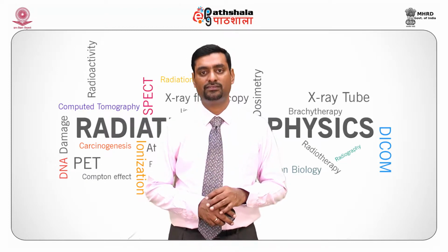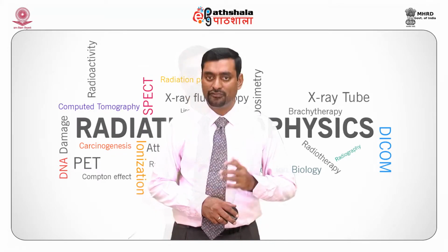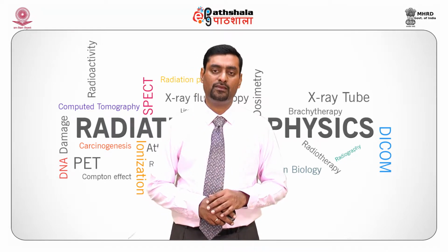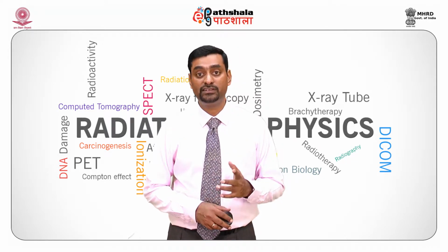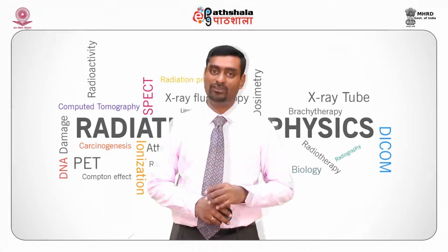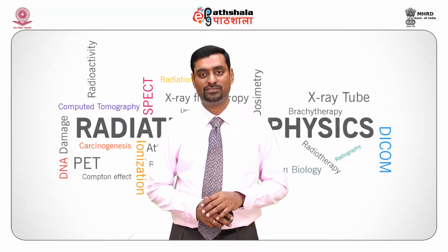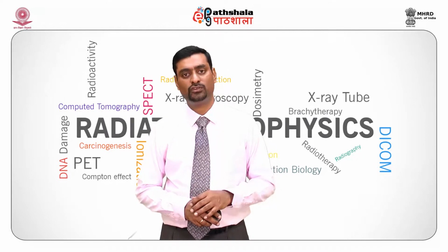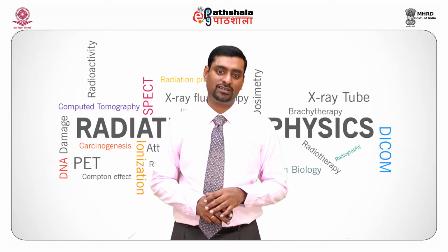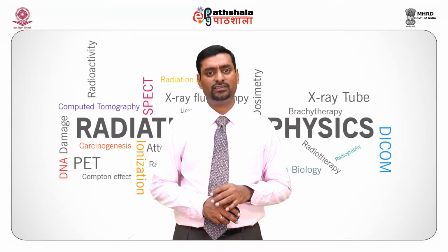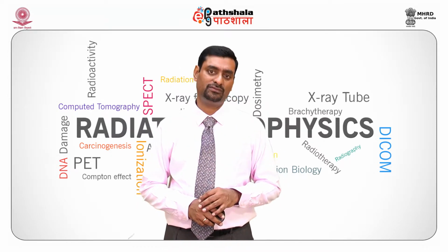What are the factors that influence image quality? Exposure factors, kVp. Let us consider the tube potential, which is kVp. High kVp increases scatter radiation, hence noise. Hence we can use grids in order to remove the noise and scatter, so that it will improve image contrast. mAs, that is the tube current-time product, is also directly related to the density of the image.